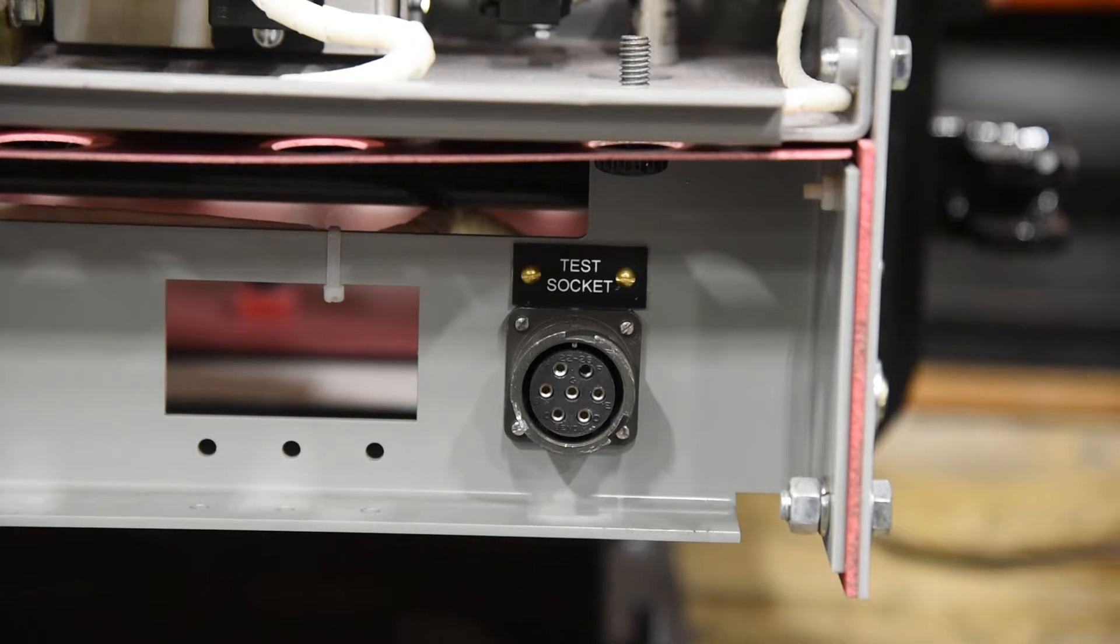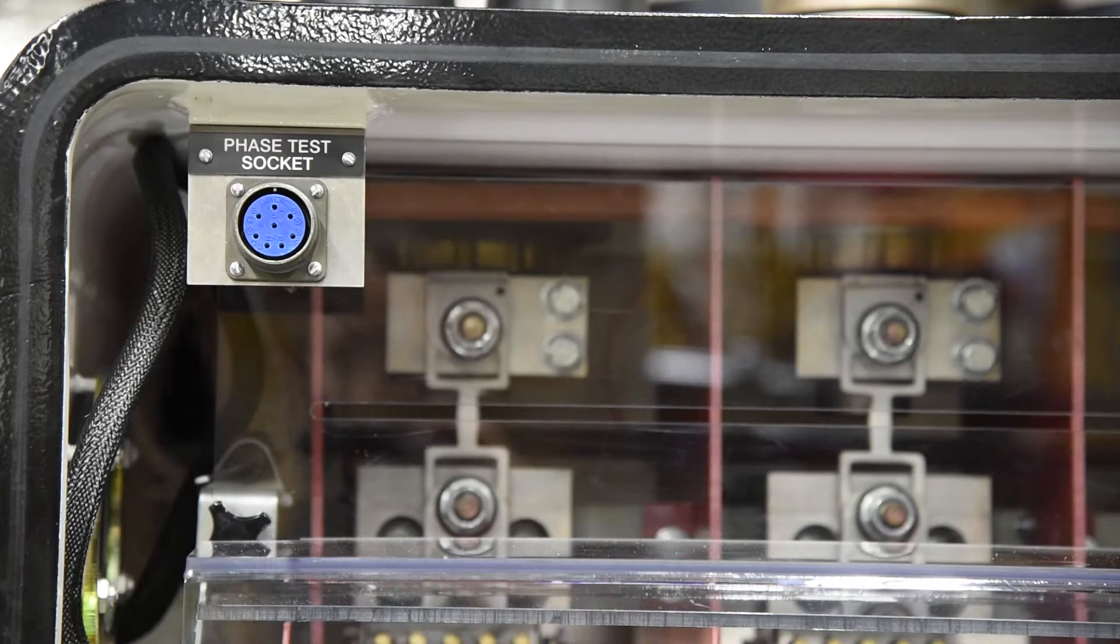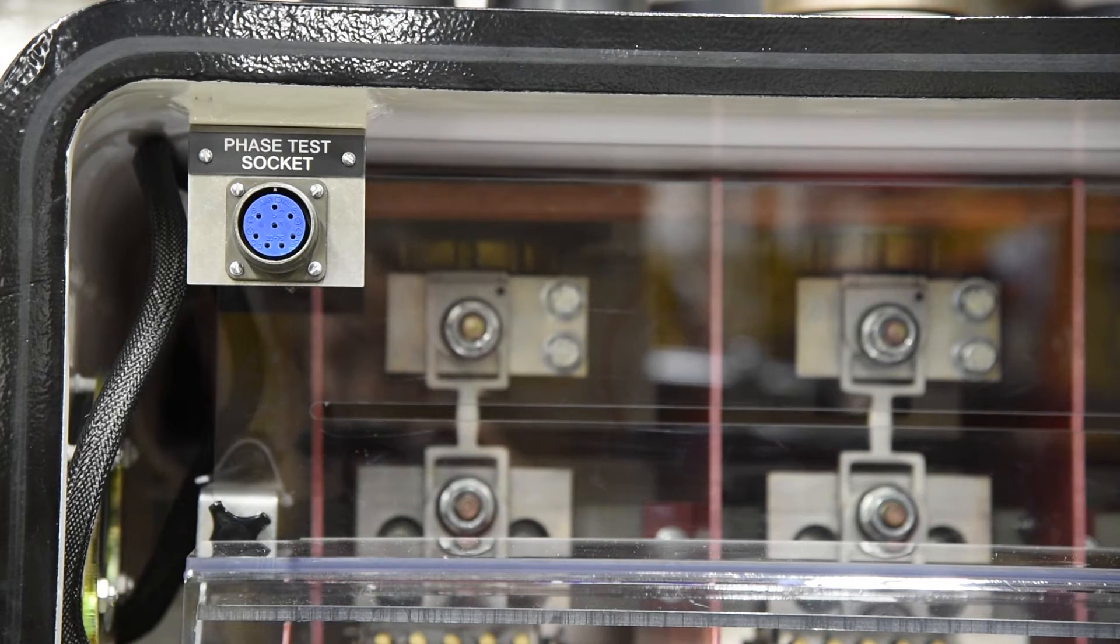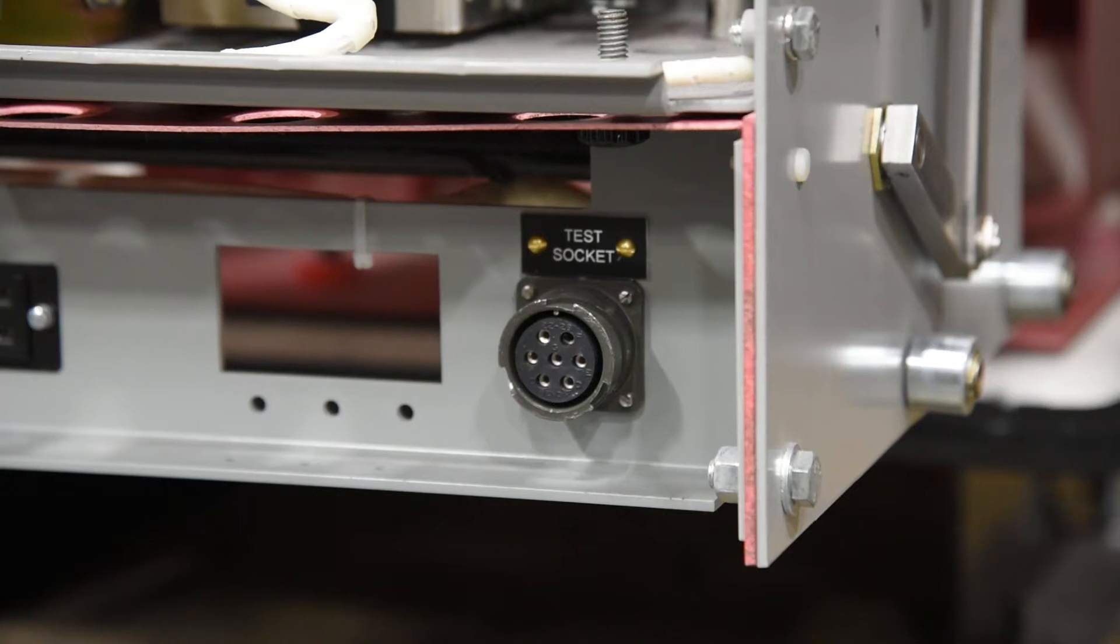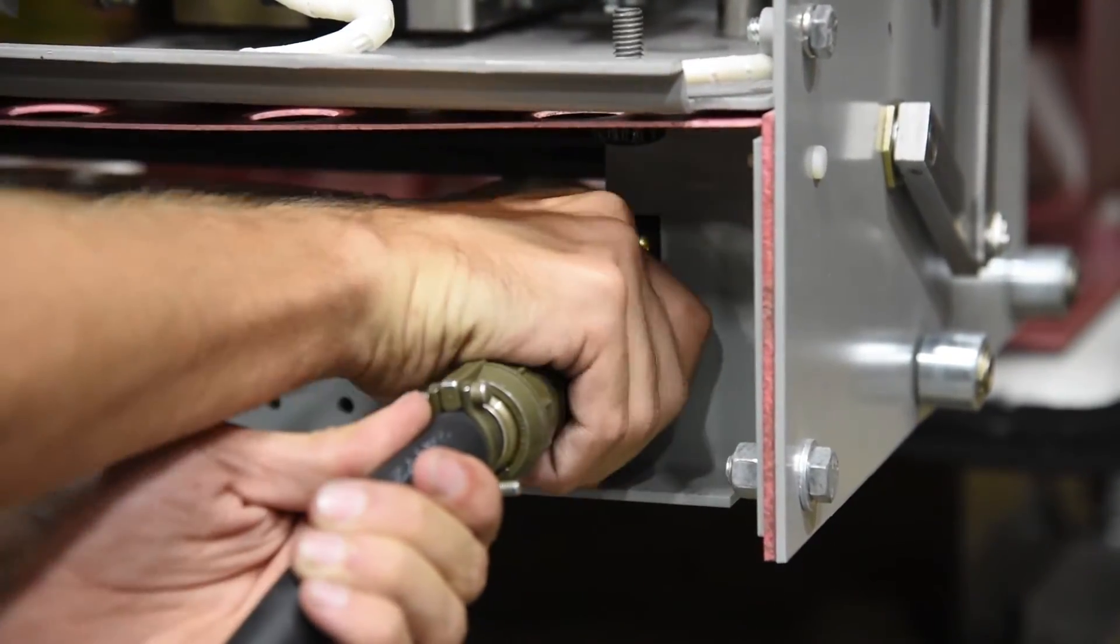Two connection sockets are available on the 416NP series to facilitate network protector commissions, testing, and preventative maintenance work. These Amphenol military grade connectors simplify connections and eliminate the need for alligator clips. A test socket comes standard on all 416NP mechanisms. It provides a convenient connection point for ETI network protector test set needs.